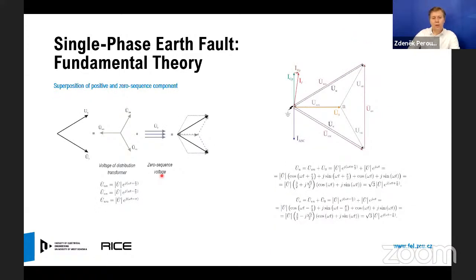When the earth fault occurs, the voltage vector diagram changes. The healthy phase to ground voltages become the line to line voltages, and we can decompose the final voltage vector diagram into the positive sequence component and the zero sequence component, to which we will pay the main attention today. That's what we are trying to address when we would like to compensate the earth fault.